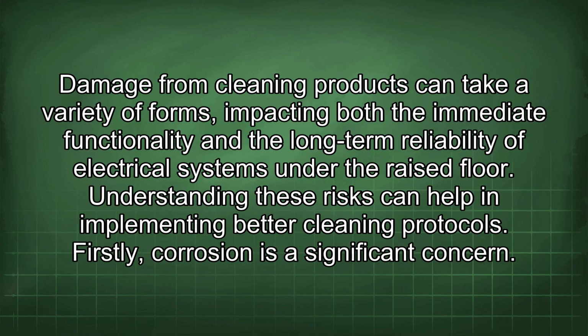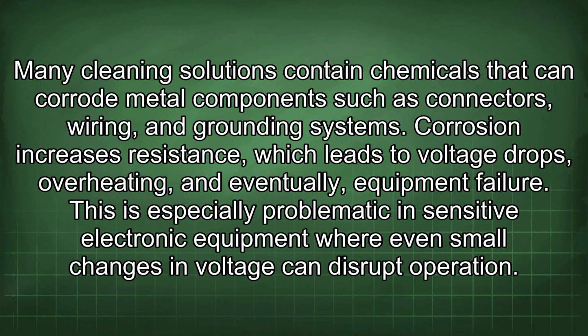Damage from cleaning products can take a variety of forms, impacting both the immediate functionality and the long-term reliability of electrical systems under the raised floor. Understanding these risks can help in implementing better cleaning protocols. Firstly, corrosion is a significant concern. Many cleaning solutions contain chemicals that can corrode metal components such as connectors, wiring, and grounding systems. Corrosion increases resistance, which leads to voltage drops, overheating, and eventually equipment failure. This is especially problematic in sensitive electronic equipment where even small changes in voltage can disrupt operation.